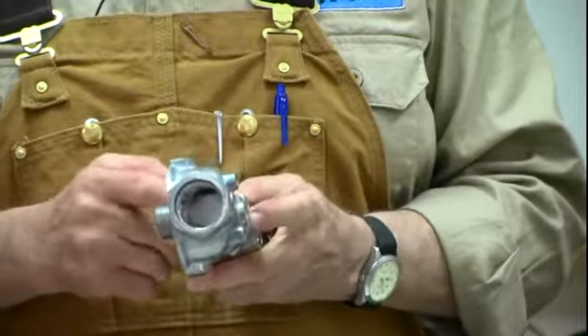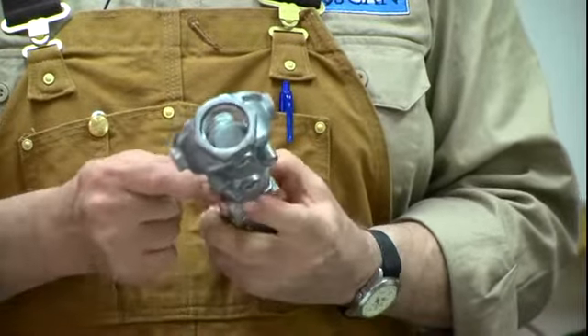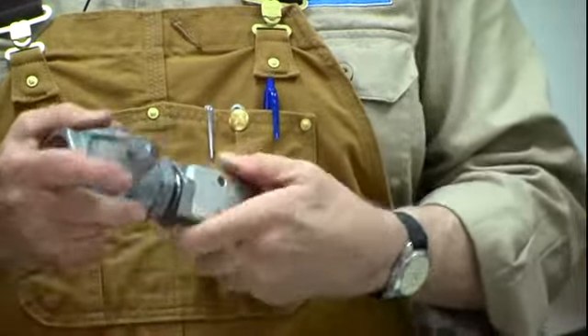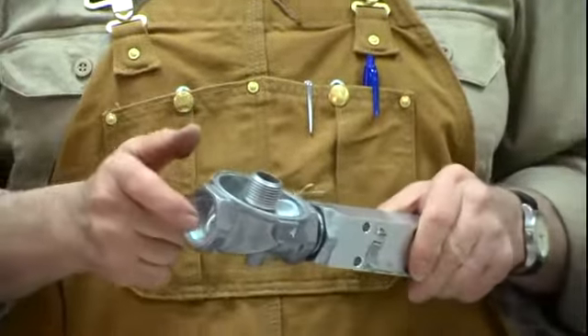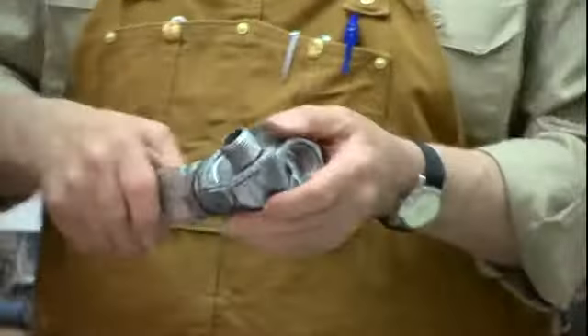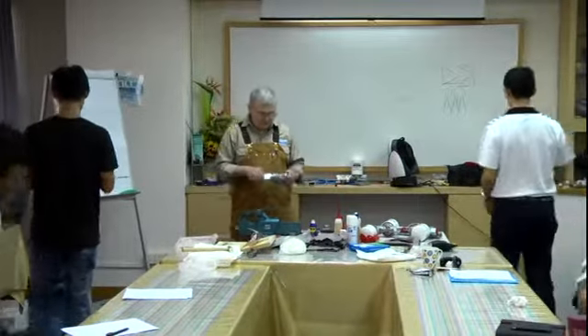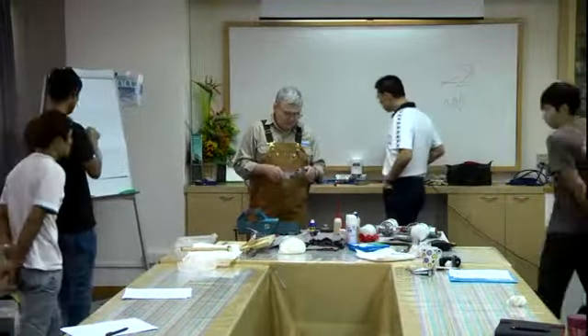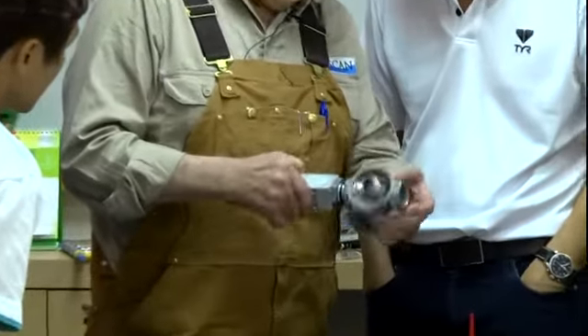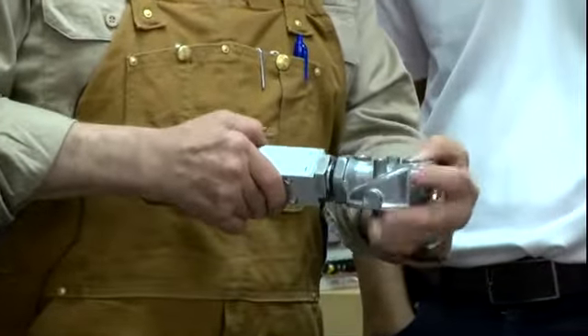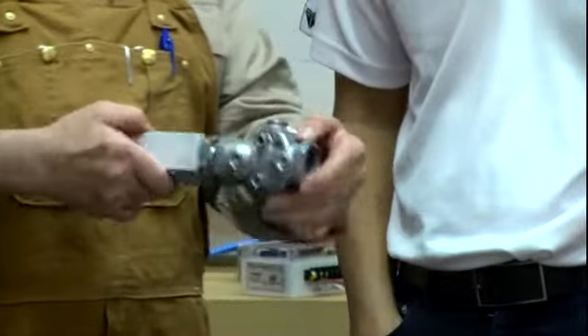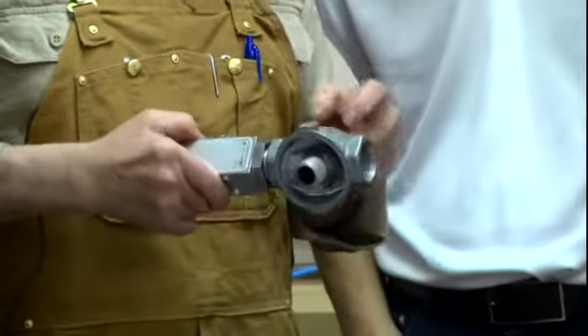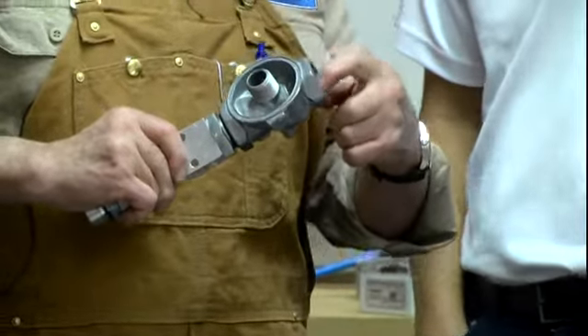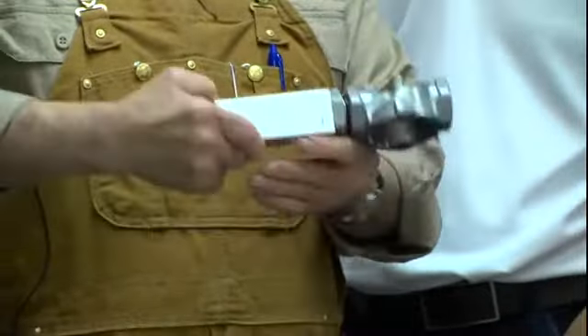You also have to remember that these are aluminum threads, aluminum on aluminum. Though they're not pipe threads, you have to turn them slowly. If you turn them quickly, they can gall. Everybody want to come up here so you can see? You need to bring this casting so that the taper is beyond the threads, so that when the jam nut or the lock nut tightens up, it's pushing against this part and not the threads. So this would be down. Let's say we have to have it off a little bit.